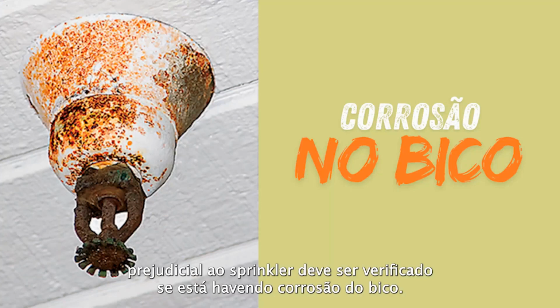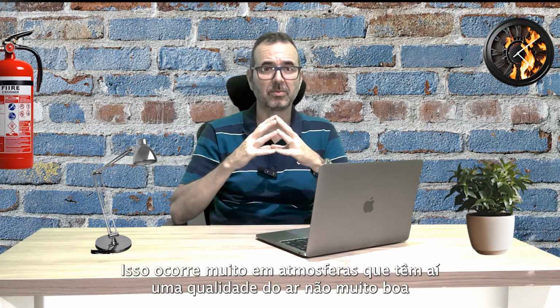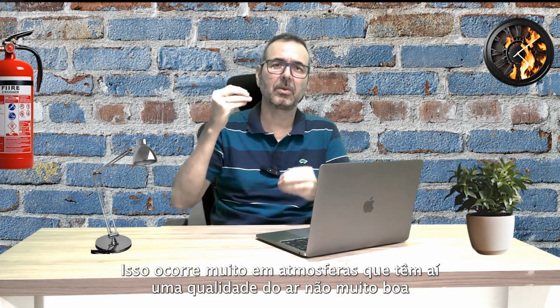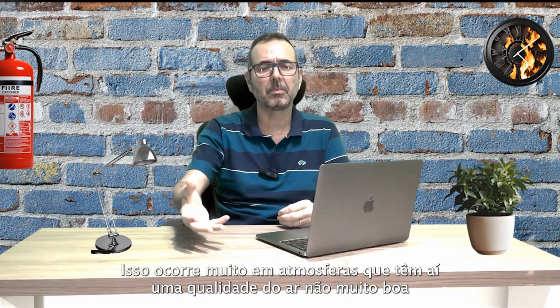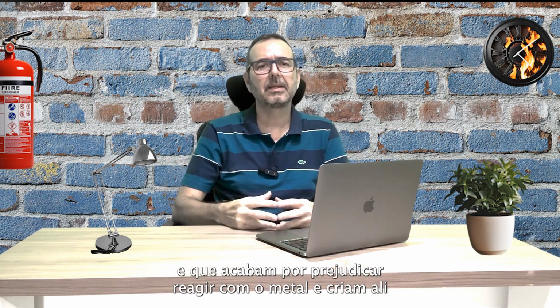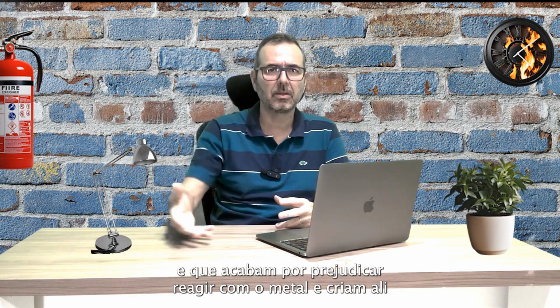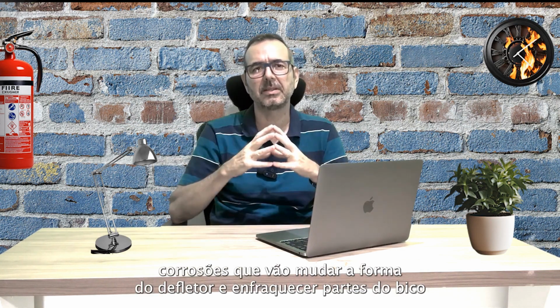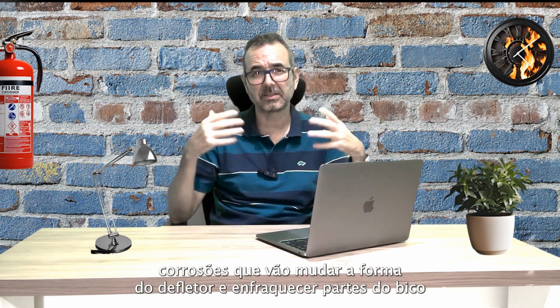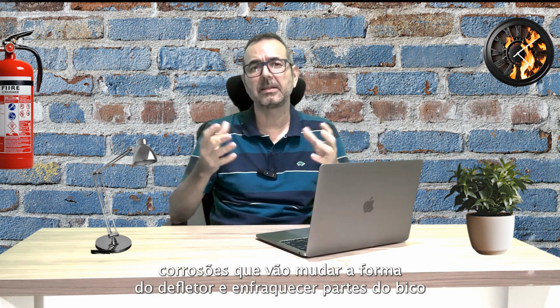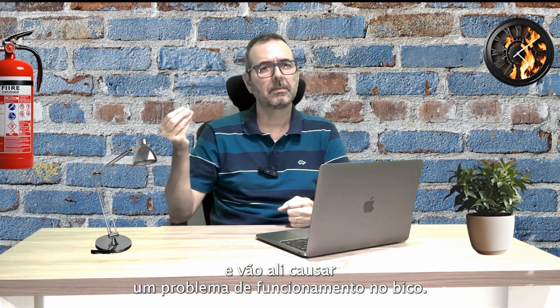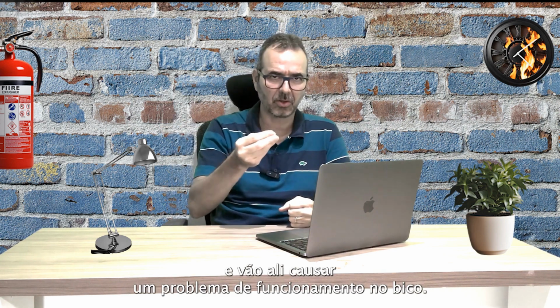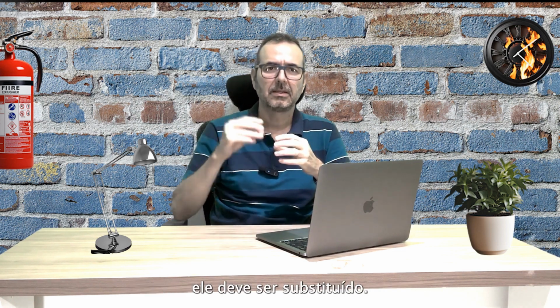Corrosion, harmful to the sprinkler. It should be checked whether there is corrosion of the nozzle. This often occurs in environments with poor air quality, which can adversely affect the metal and create corrosion that alters the shape of the deflector, weakens parts of the nozzle, and causes operational issues. Therefore, any nozzle that shows signs of corrosion should be replaced.